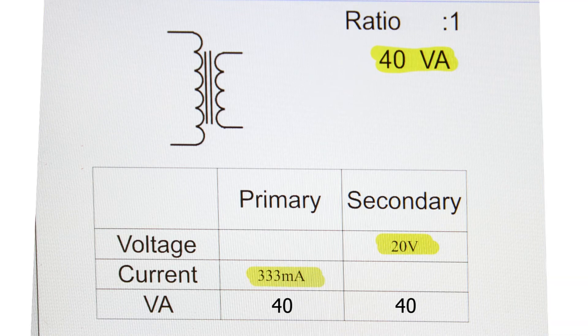40 volt amps on primary and secondary. 40 divided by 333 milliamps is 120 volts. If we have 20 on the secondary, that would be a 6 to 1 ratio. Take the 40 divided by 20 volts to get 2 amps of current on the secondary.